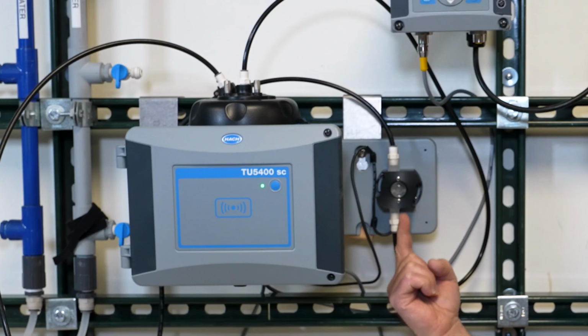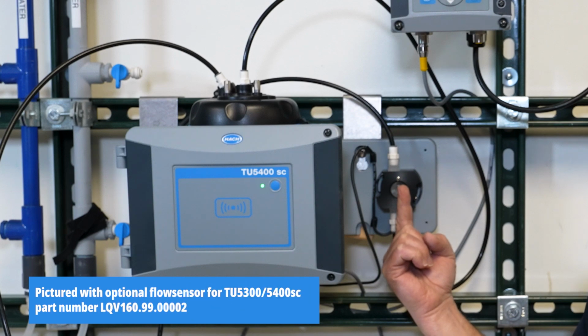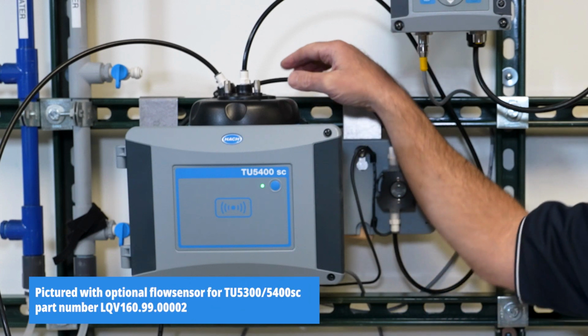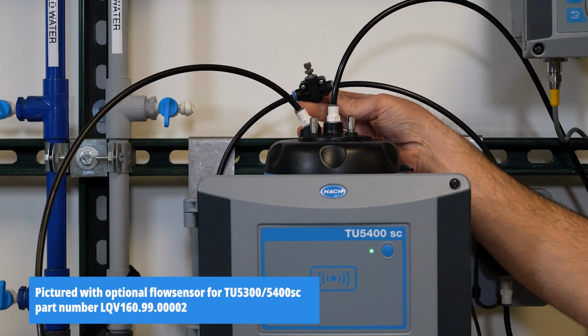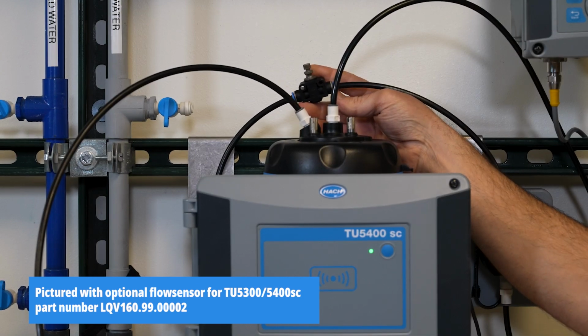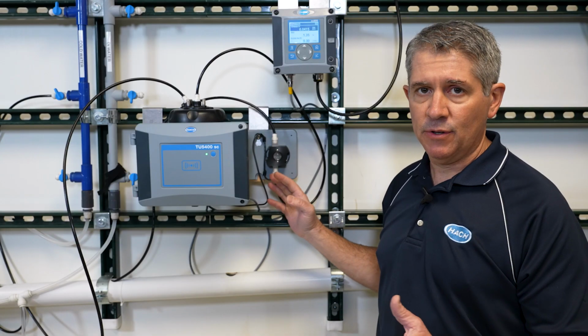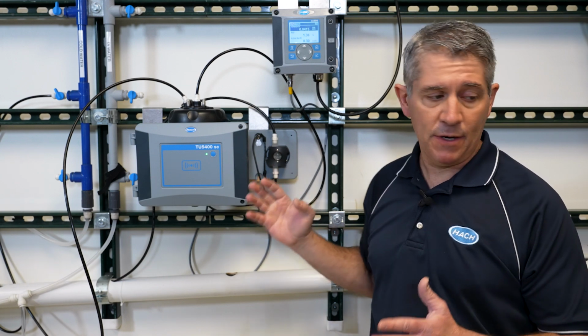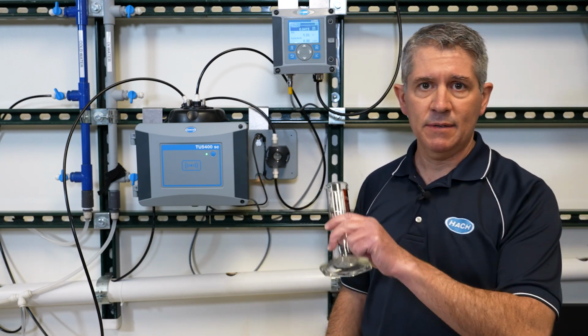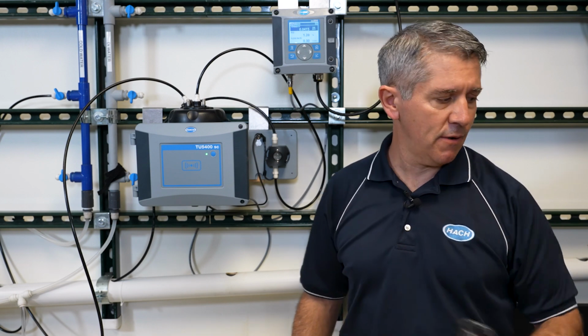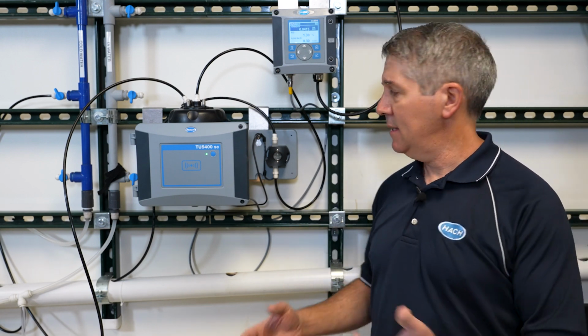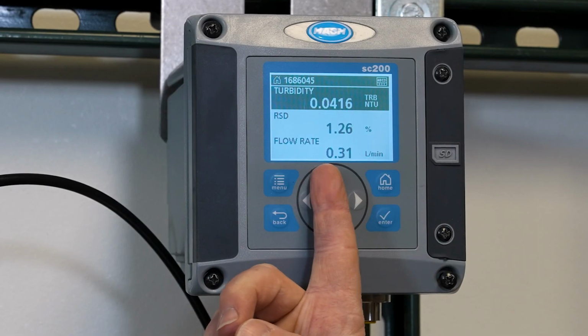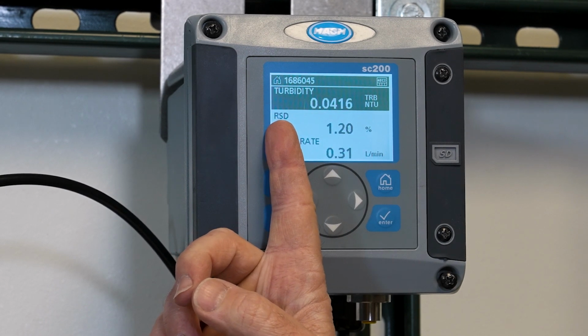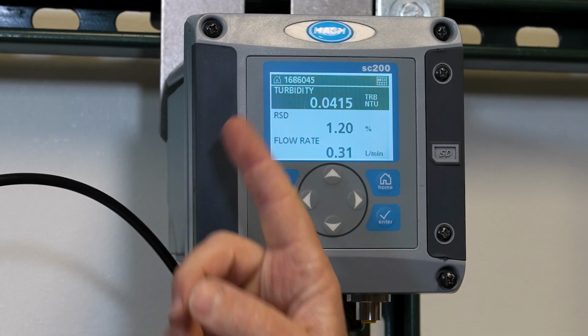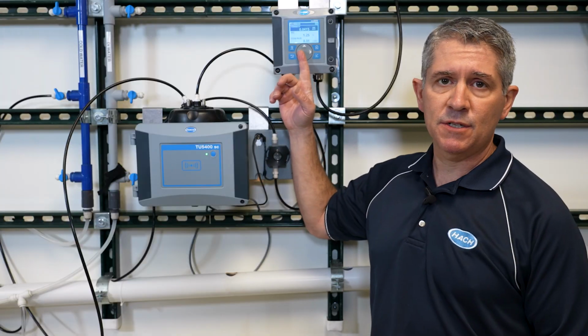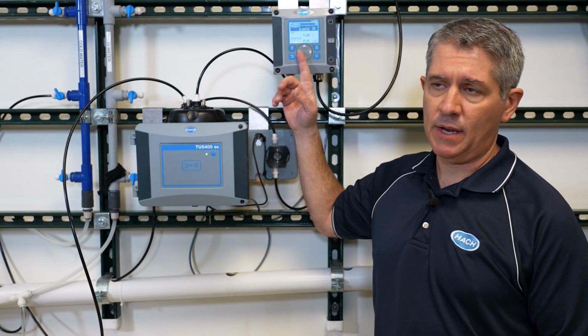So you go up through the flow regulator here, and it comes out, and then it goes to a back pressure regulator. So the flow regulator isn't essential. This is optional. If you don't have one, you could always just do a quick flow rate test with a graduated cylinder or something like that. But it's really nice to have it. You have the flow rate displayed up here, as well as the RSD and as well as the turbidity. You can also even map this to your own 4-20 if you want to, which is pretty handy.